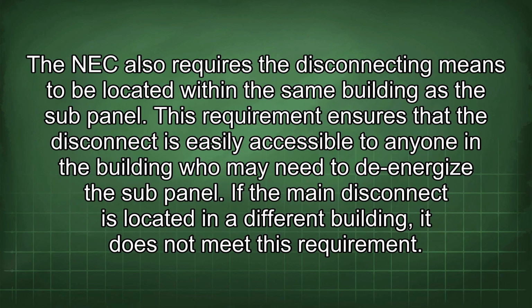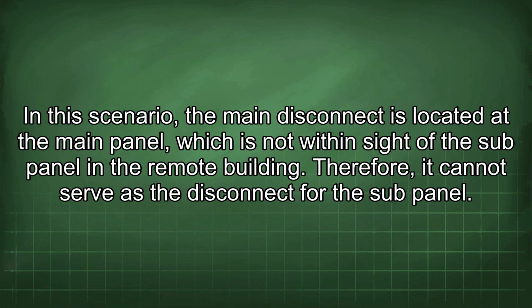The NEC also requires the disconnecting means to be located within the same building as the sub-panel. This requirement ensures that the disconnect is easily accessible to anyone in the building who may need to de-energize the sub-panel. If the main disconnect is located in a different building, it does not meet this requirement. In this scenario, the main disconnect is located at the main panel, which is not within sight of the sub-panel in the remote building. Therefore, it cannot serve as the disconnect for the sub-panel.